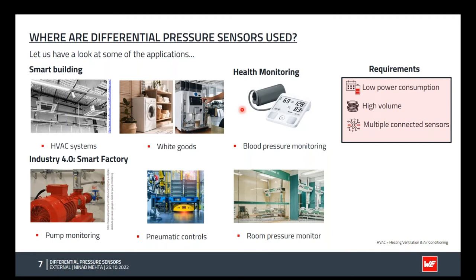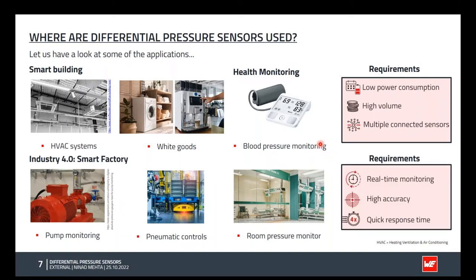In industrial applications or the smart factory, pressure sensors are employed for pump monitoring, pneumatic controls or robotic arm controls. Another interesting application is room pressure monitoring, for example for operation theaters or clean rooms, where the room should have a higher pressure than the corridor so that bacteria or contaminants cannot enter and the environment inside is always clean. For these purposes pressure sensors are used, and these applications require real-time monitoring so that you can always see the status of the system. They should have precise, accurate measurement, and they should also respond quickly to pressure changes.